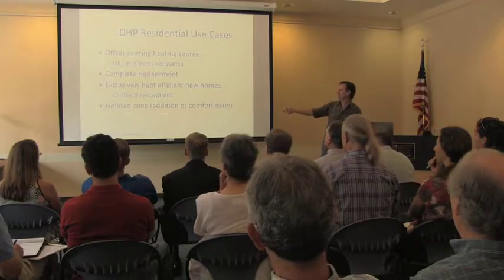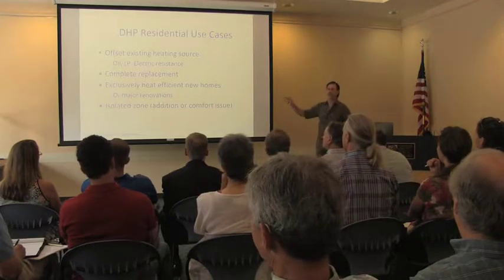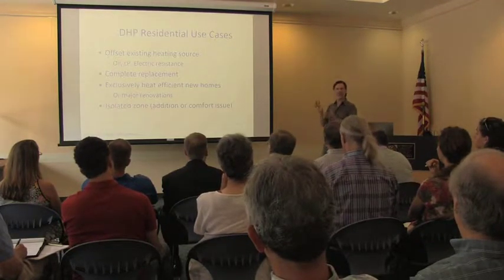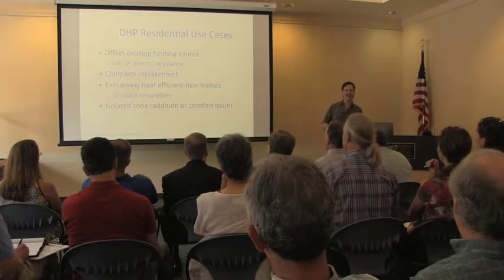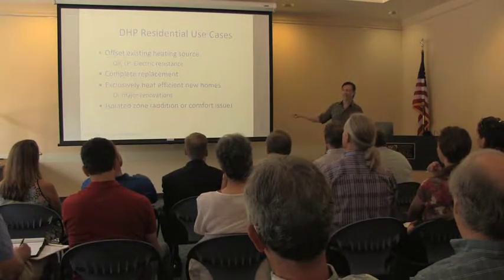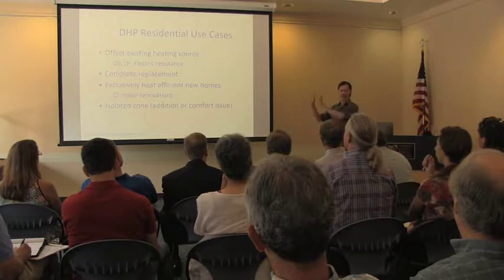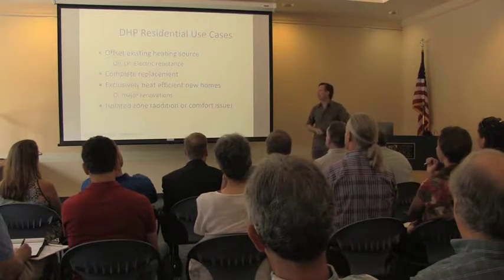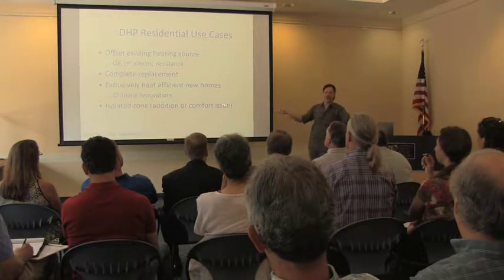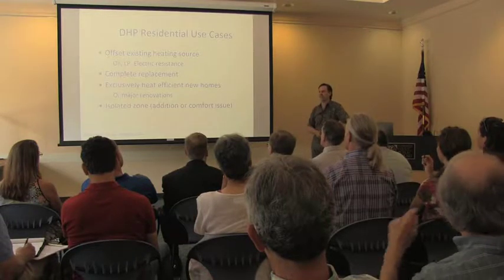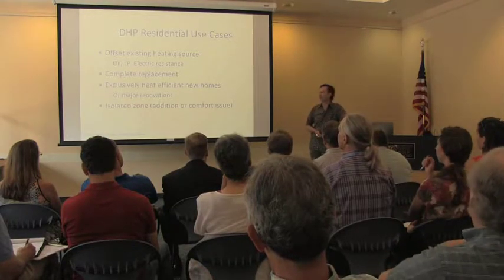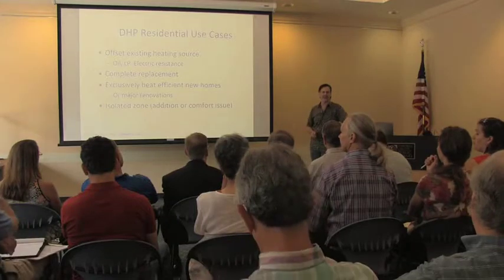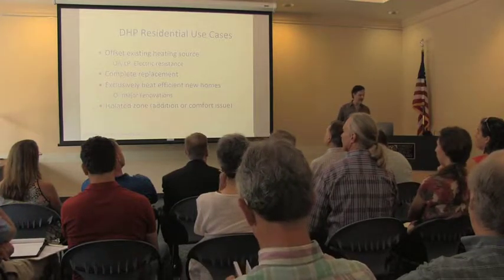Certainly an isolated zone, like if you've got a bonus room over a garage that just never got heated and cooled properly, it's not comfortable. An addition is often that kind of situation. Somebody adds a family room on the end of their house. That could be a great application, even if your existing heating system works fine and you don't want to mess with it. You could just add a single zone heat pump for that space.